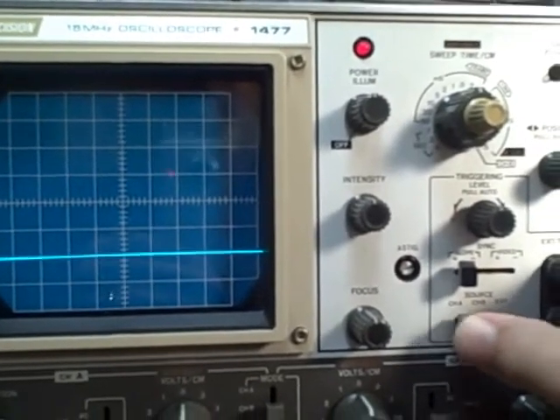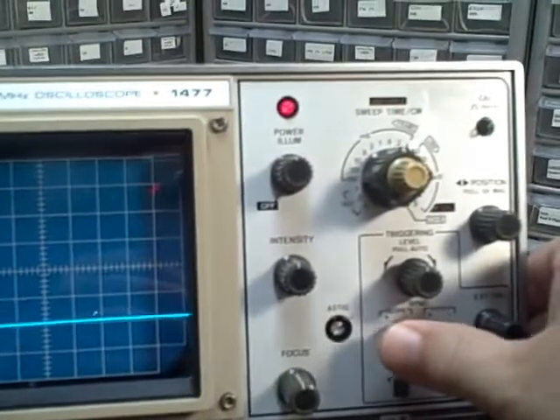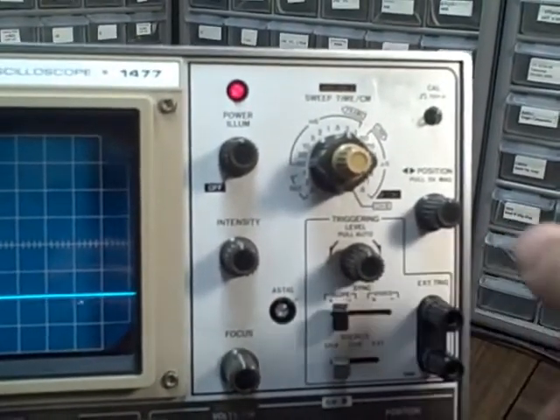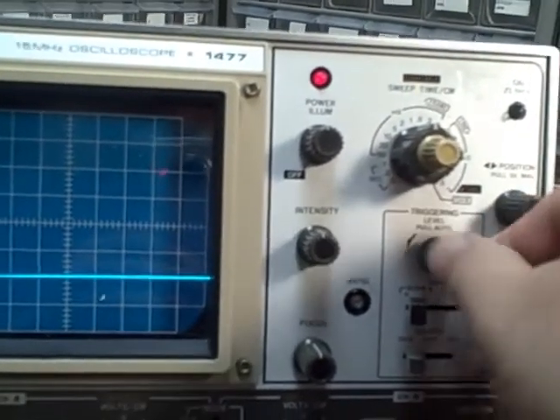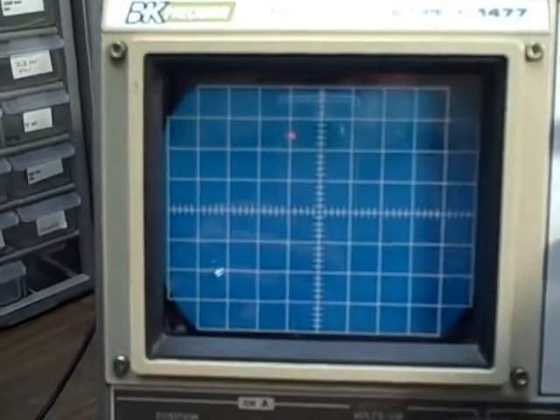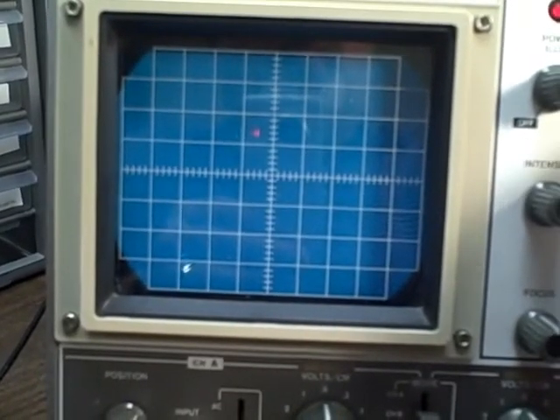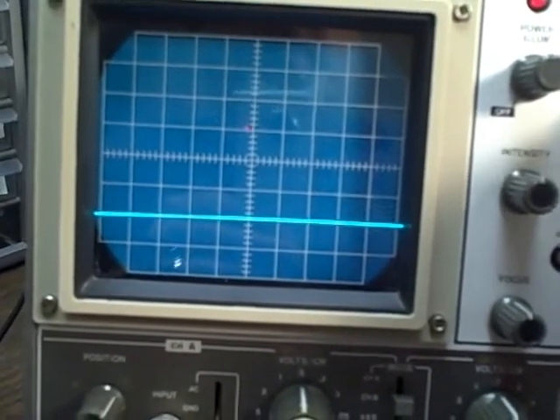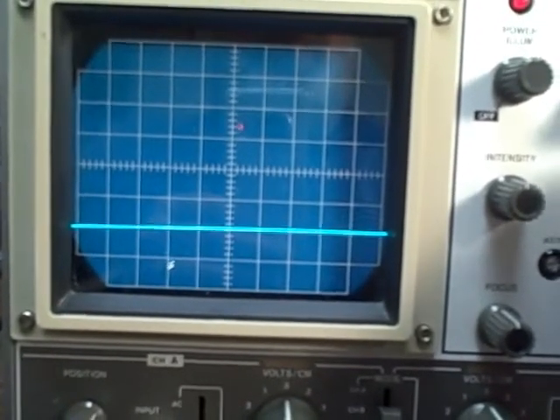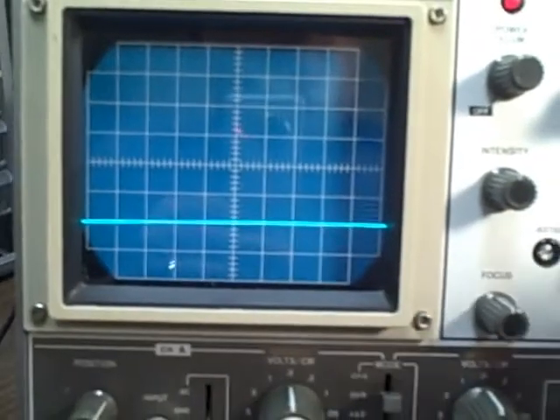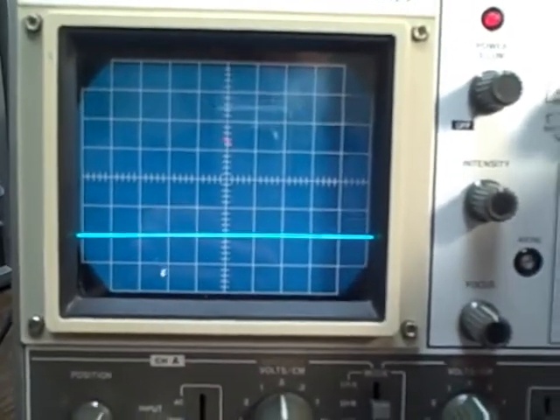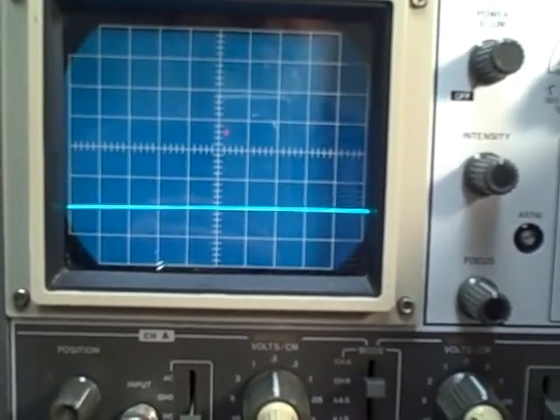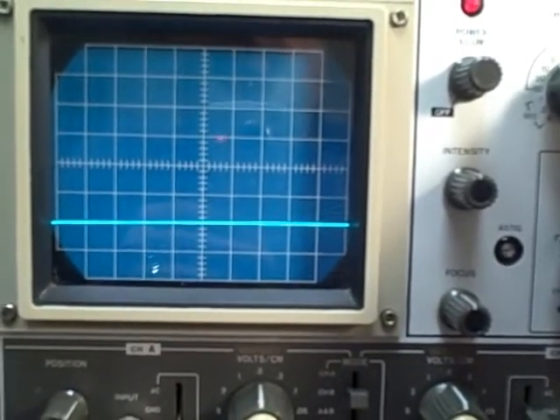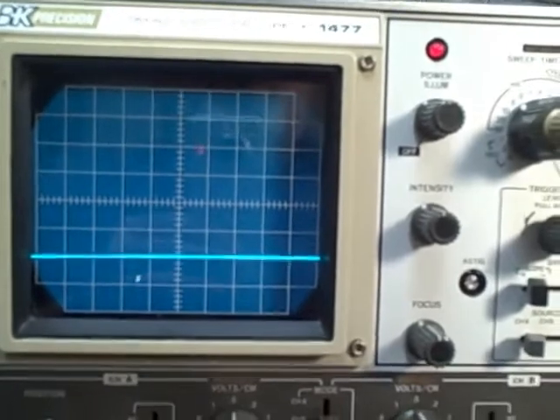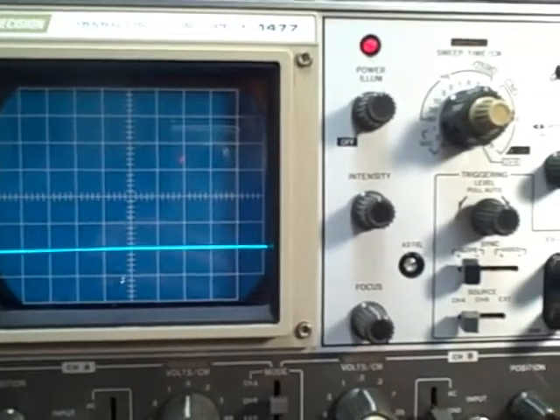And we can change our trigger source from channel A to B, or external. We can change our slope from positive to negative. We can change video input from positive to negative. We have triggering for the scope. It can either be in normal mode, where you have to have a signal in order to get a trigger. That's the way that works. Or we can go into automatic, where it'll run. You'll see something all the time. I normally run in auto like that. And then we have the horizontal centering. It's working just fine. The magnification, which we demonstrate during the calibrations, you'd have to have a signal on here for you to see it. So that's some of the basic things.